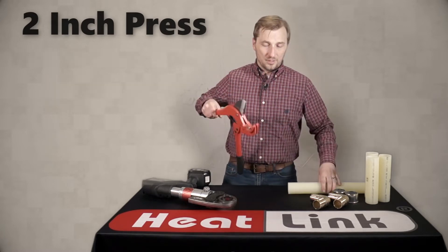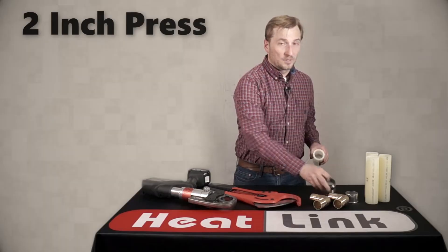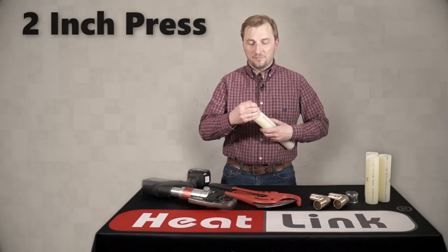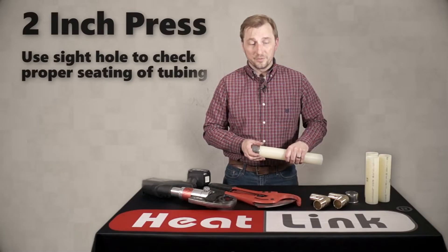As always, make sure that you cut your tubing at a 90-degree angle. This will help to ensure that the sleeve seats properly, and use the sight hole to make sure that it has seated properly on the tubing.